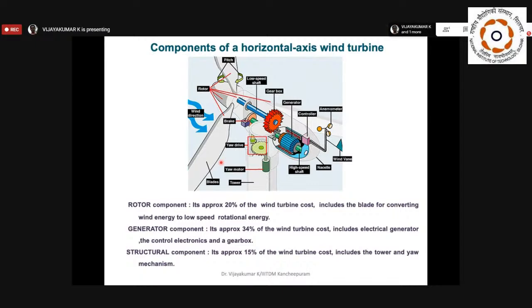The speed of a wind turbine in real time is 10 to 50 RPM. So if you go with more blades, the speed range will come down again. If the speed range comes down, then the gearbox stages will increase. So by increasing the number of blades, the cost increases. At the same time, if you increase the gearbox stages, the cost will go up again. Adding together, the entire cost of the system will be higher. That's why they don't prefer more blades in the wind turbine system.